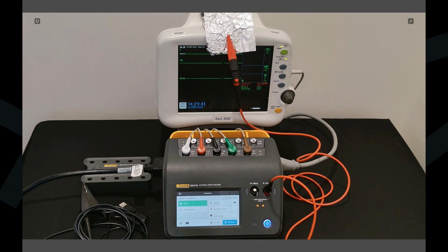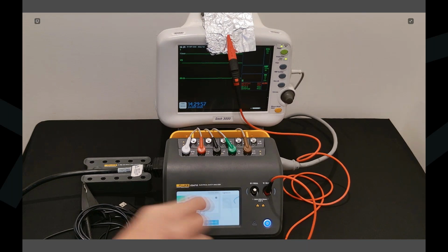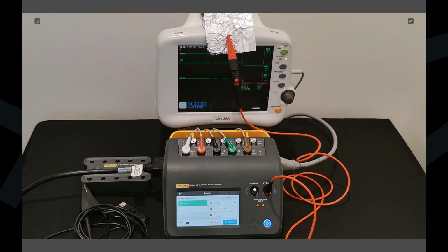So one more thing before we finish our test, back to the biomed validation, we're going to sign this work order right from the instrument. That's letting me know I did it. Another cool thing that you can build within OneQA, if the biomed guys are out there doing field service, or you're in clinics, or if we have a field service team, you could set up 2 lines of signature to where the biomed or the field service engineer can sign off on the test. Also, the customer could sign off on the test. So you'd have 2 levels of signature, and it would all go into your PDF work order. So once that's done, you would hit complete.